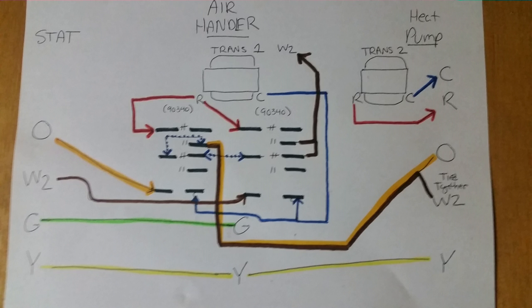And even in cooling, as you see, there's a W2 brown run to the other coil and the red to the top of the W2 relay, we'll call it the one on the right, the W2 relay. If you have a thermostat that uses electric reheat, it will still energize those heat strips just like it would otherwise when the W2 and common energize the second 90340 double pole double-throw relay.